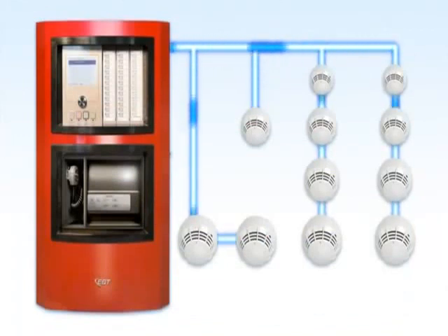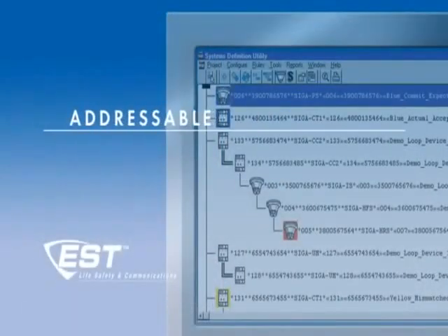All Signature Series devices are externally supervised by the control panel. The Signature Series detector's intelligence can even provide an alarm in the unlikely event of a loop controller CPU failure. Our Signature Series technology deploys distributed intelligence, allowing it to make a decision independent from the control panel. Essentially, if the control panel fails to poll the Signature device, the Signature device reverts to an intelligent conventional device, allowing the product to produce a loop alarm and still evacuate the occupants. So we have our detectors make the decision, we have our control panels make decisions, but the key here is survivability.